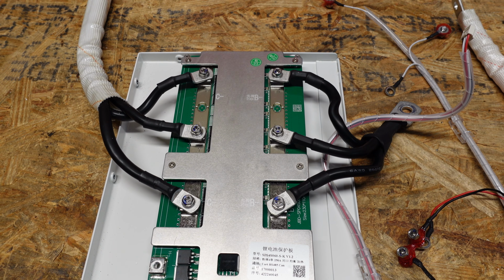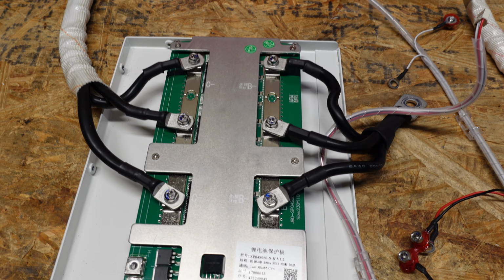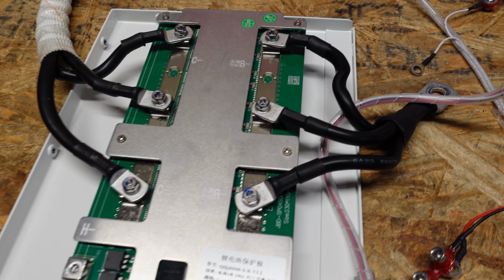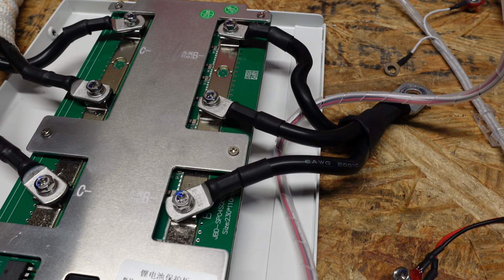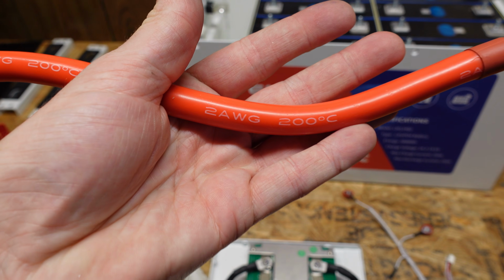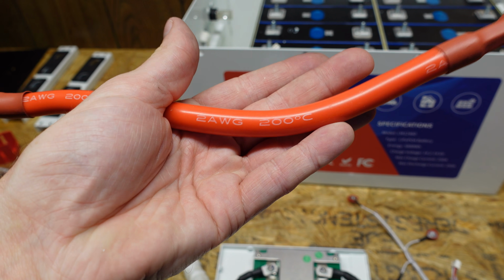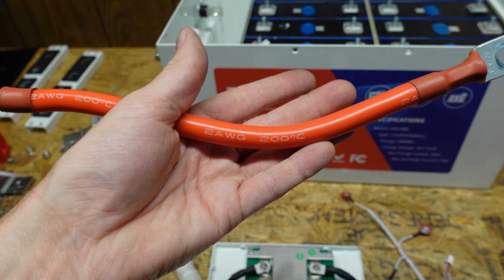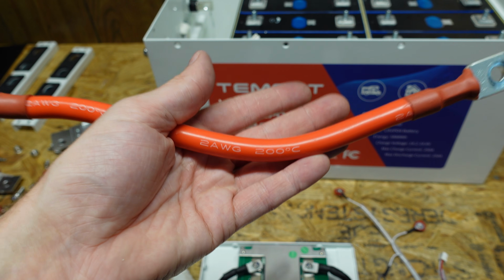Our battery cabling on the negative side is comprised of three 6-gauge conductors. It is silicone insulated cabling with a 200 degrees Celsius insulation rating. On the positive side here, we have a piece of number 2, or 2-gauge, cable - also 200 degrees Celsius insulation rating.